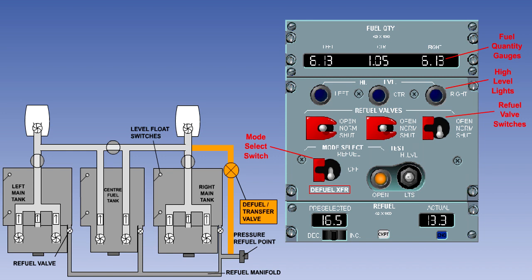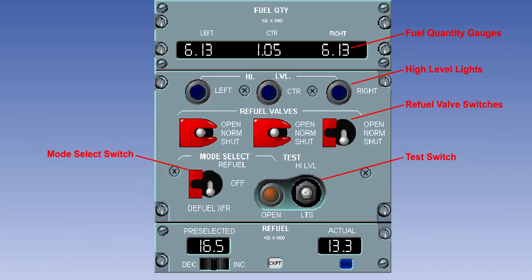The amber open light will illuminate. The test switch is a three position switch spring-loaded to the center off position. When it is held to the high level position, operation of the high level float switches or volumetric top-off units is tested. If they are serviceable, the blue high level lights will illuminate.